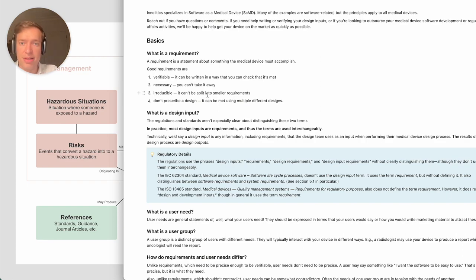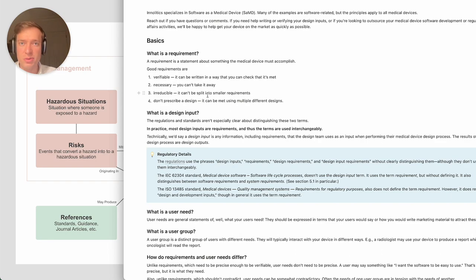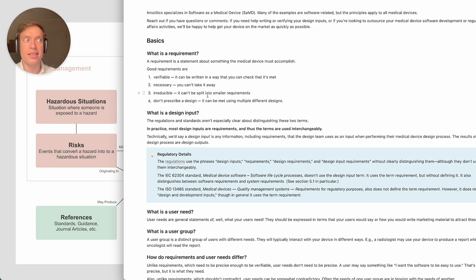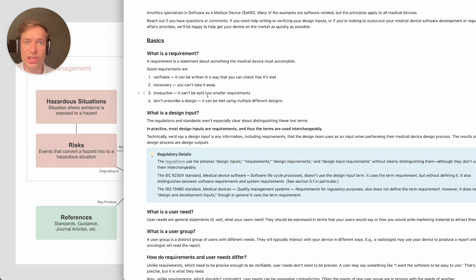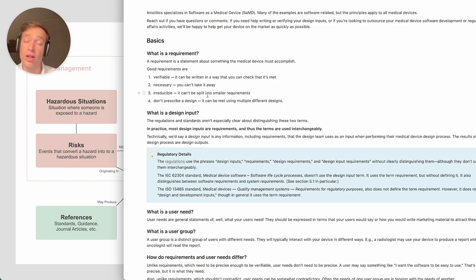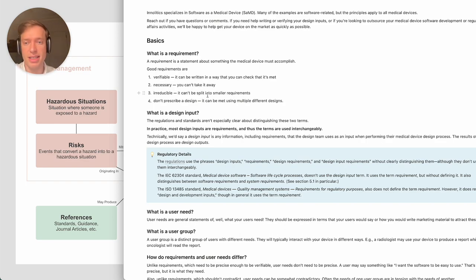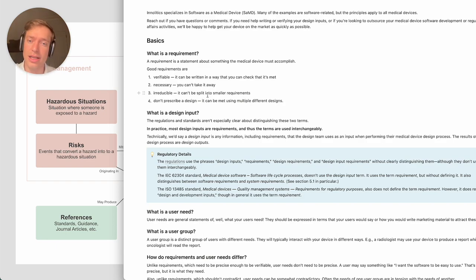If there's several paragraphs, it probably has a lot of things in those paragraphs that the device must do. How can you check that each one of them is checked? It's easier to split it up into a bunch of smaller irreducible requirements and then trace the verification to each one of them at a time. That's not something you have to do, but it's just a good best practice.